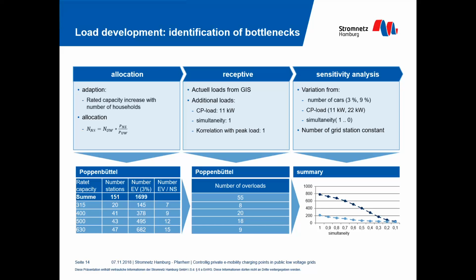The second scenario assumes 9% of all cars in Hamburg are private EVs loading at private infrastructure. The interesting numbers are 200 and 800. In the first scenario, 20,000 private EVs loading at private infrastructure will cause 200 bottlenecks in our grid. We have 6,000 transformer stations in Hamburg, so 200 of these will have a bottleneck in the 0.4 kV grid.